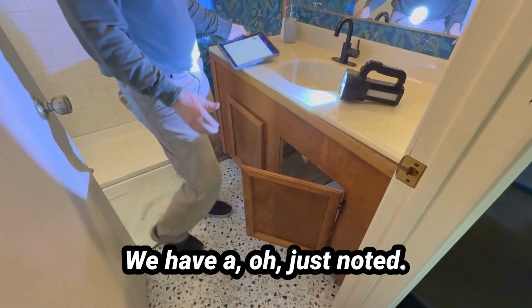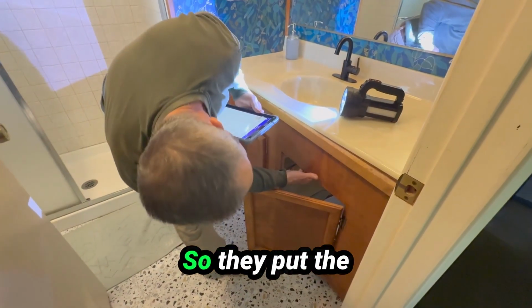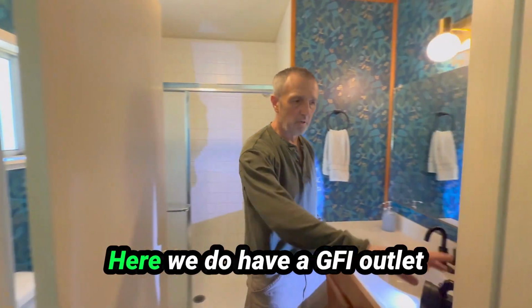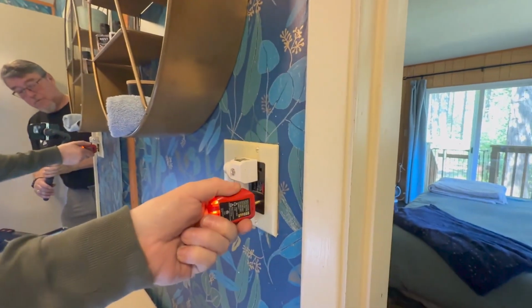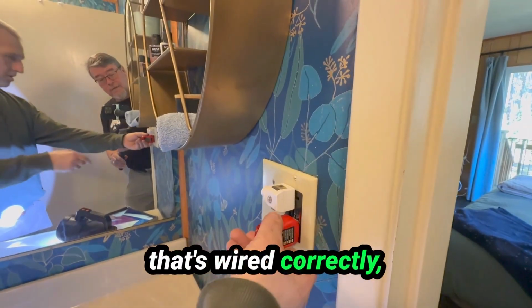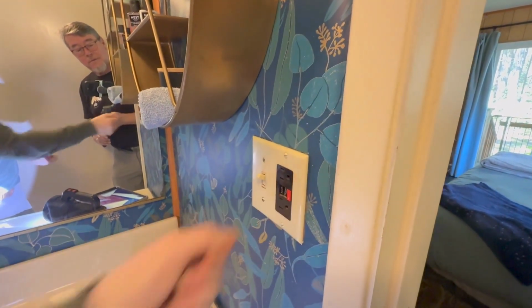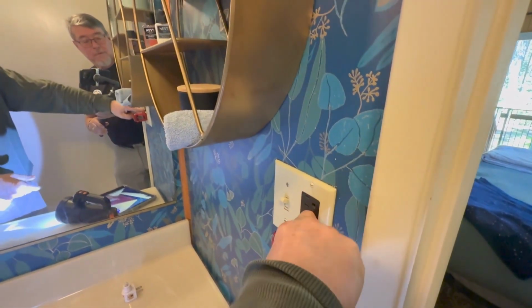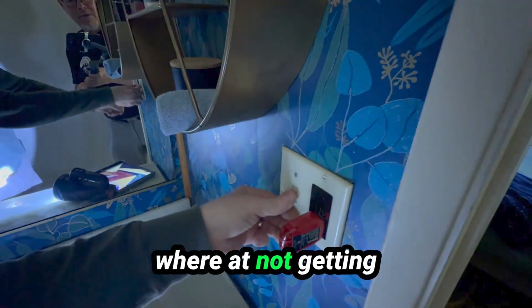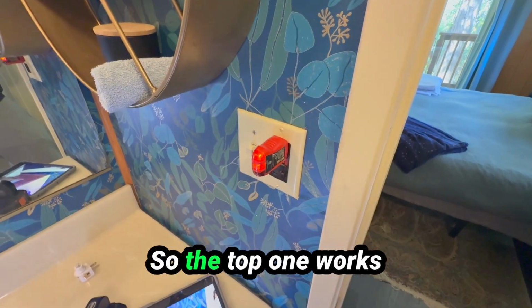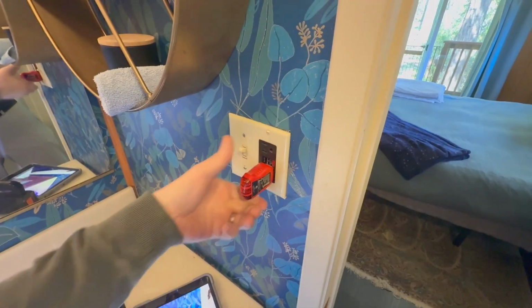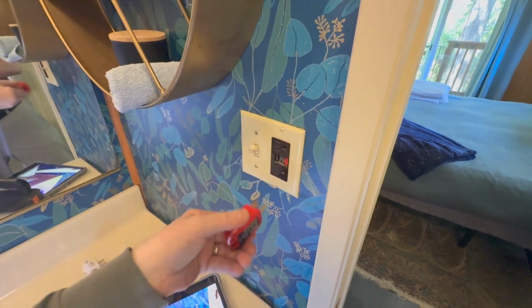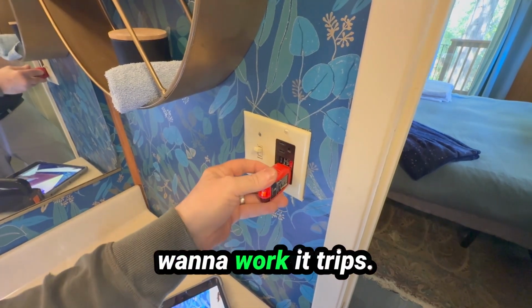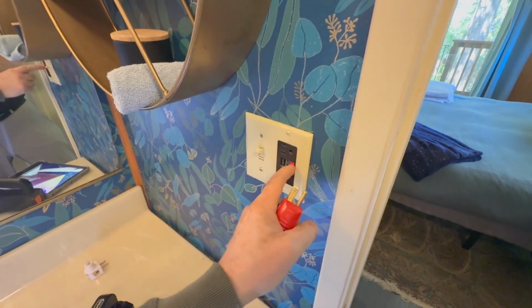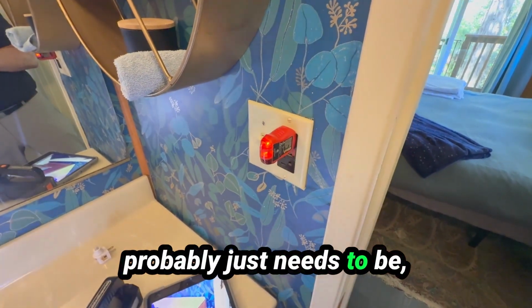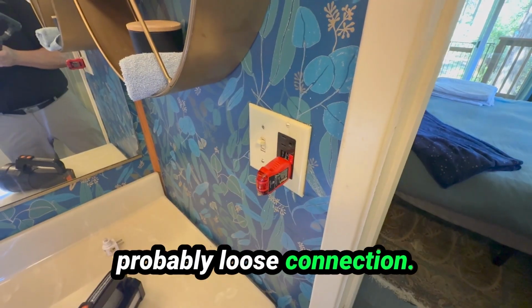We have a, just noted, so they put a screw right there. Here we do have a GFI outlet. That's wired correctly. We're not getting anything on it. So the top one works. And the bottom one won't work. It trips, so it's a wiring issue, but probably just needs to be taken out and I would say probably loose connection.